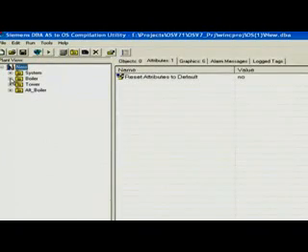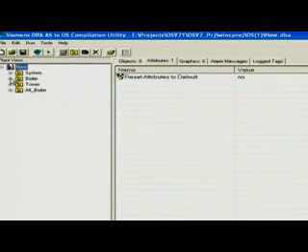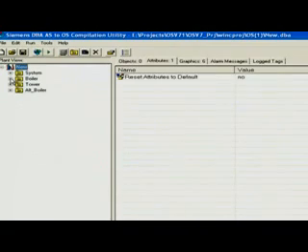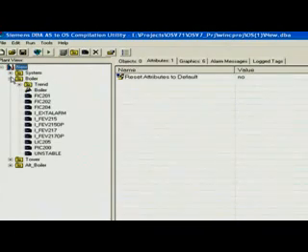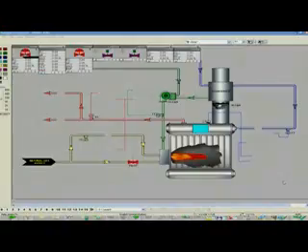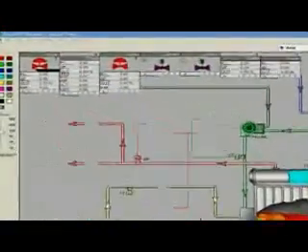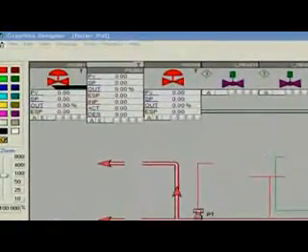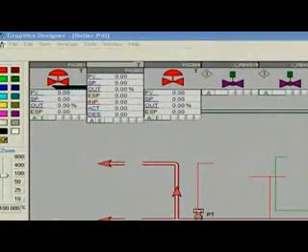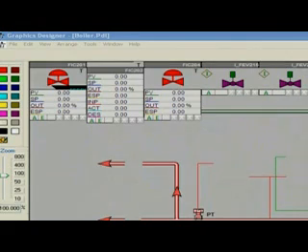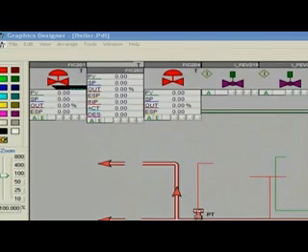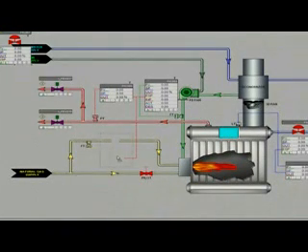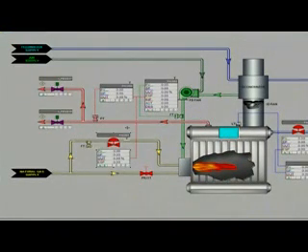DBA has a GUI that allows the user to assign loops to plant areas and the associated process operations within each area. As DBA is compiled, the symbols are automatically placed onto the correct graphic picture, and the symbols are linked as defined within the plant view to the tag database. Once the symbols are on each graphic, the engineer just has to move the symbols into the correct position on the graphic, like this.